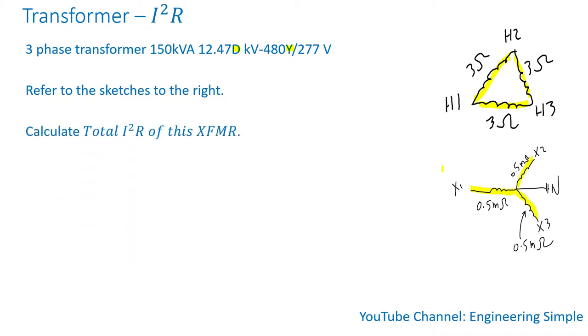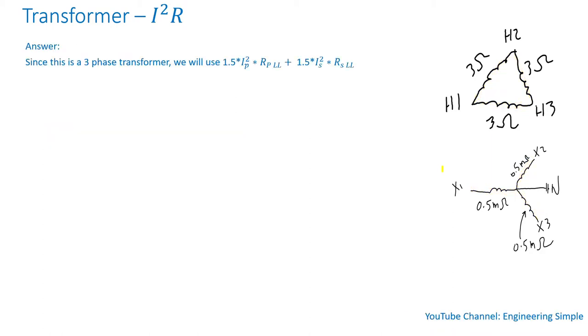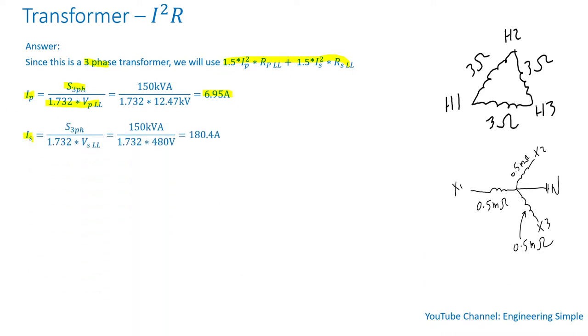Let's calculate the total I squared R of this transformer using the three-phase formula. First, the line current of the primary is the three-phase apparent power divided by the square root of 3 times the line-to-line voltage of the primary, giving 6.95 amps. For the secondary, the same formula gives 180.4 amps.